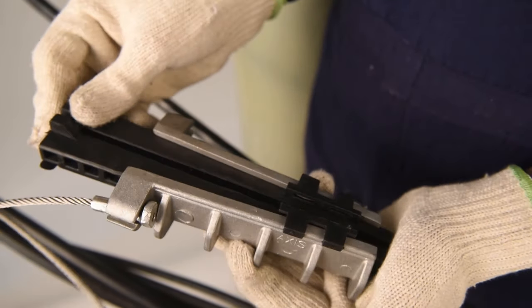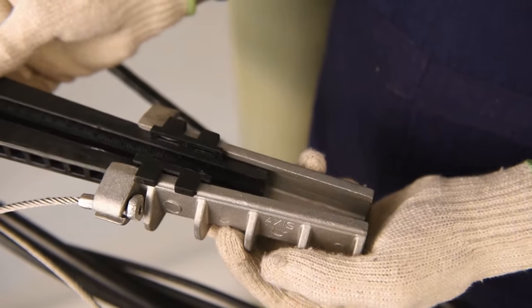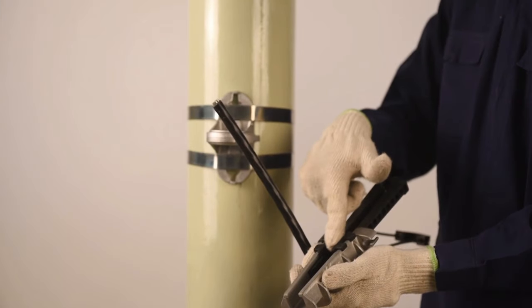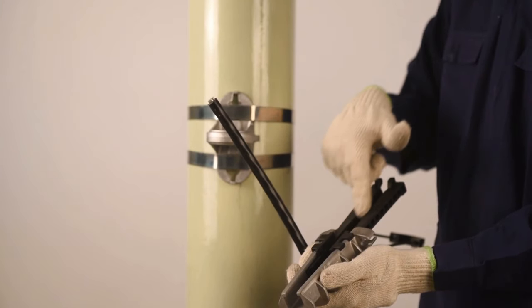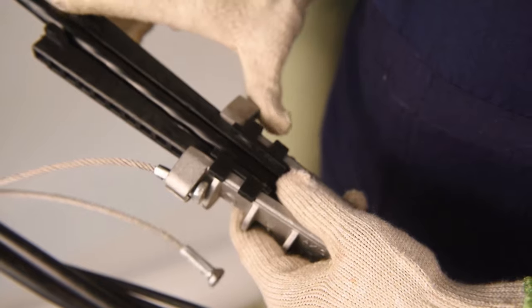Slide the captive wedges in clamp body to the top which allows sufficient gap for the cable to insert. Place the neutral messenger cable between the plastic wedges of the clamp body.